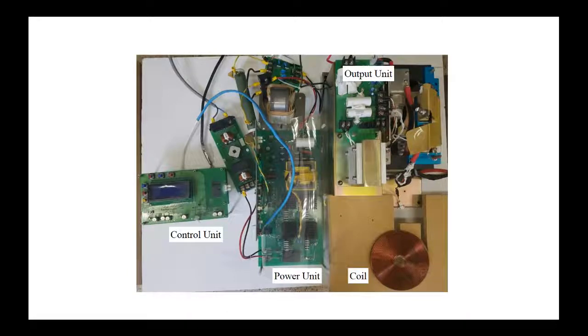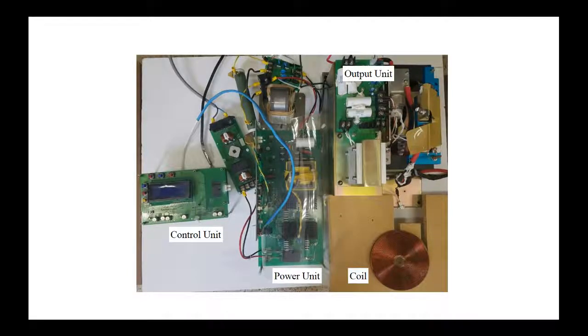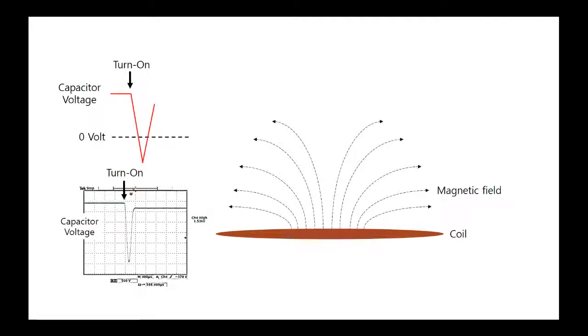The magnetic field is generated from the coil. To generate a time-varying magnetic field, a high voltage must be injected to the coil in a short time. The power unit of our system converts alternating current from a power outlet into direct current high voltage, which is stored in a capacitor. After the high voltage is charged, a discrete electric power switch turns on and the energy flows into the coil, at which point a time-varying magnetic field is generated.